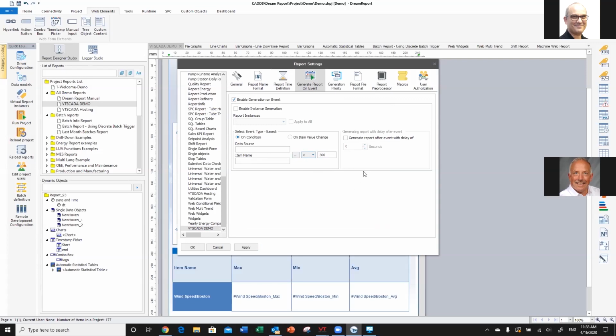If we're doing alarm reporting, we have the ability to delay our report generation to make sure our alarm messages got stored properly so that we could query them. So I might delay 60 seconds in order to generate my report, including the latest alarm information.